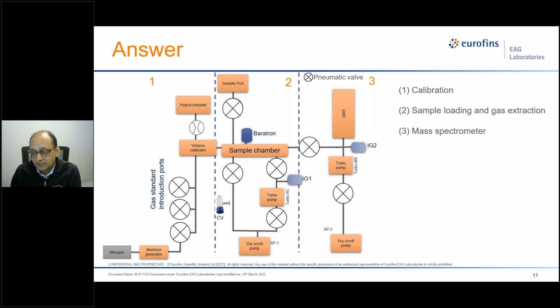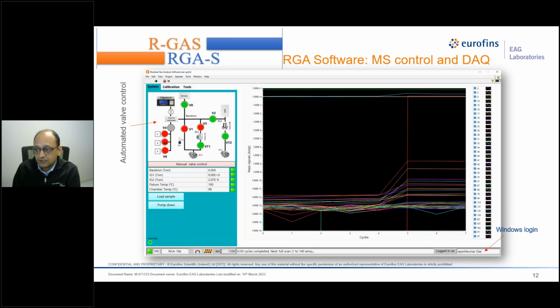Now, the third section is where the mass spectrometer is, and the mass spectrometer is in an isolated volume. There is a valve between section 2 and section 3, which keeps the mass spectrometer always isolated from the left side of the unit. Because of that, the mass spec volume is ultra clean, and it is pumped 24/7 through a turbo pump and the same kind of dry scroll pump system. Normally our mass spectrometer is in the range of 10 to the power minus 9 to 10 to the power minus 10 torr, and that is monitored by IG2, which is ion gauge 2. We also monitor these values when we introduce the sample gas to the mass spec. The change in IG2 is critical for us to confirm that we are actually analyzing the sample gas. So I would like to show the next slide where we can see that.